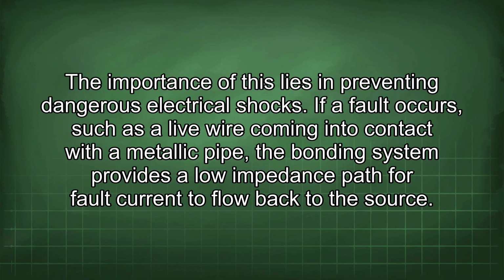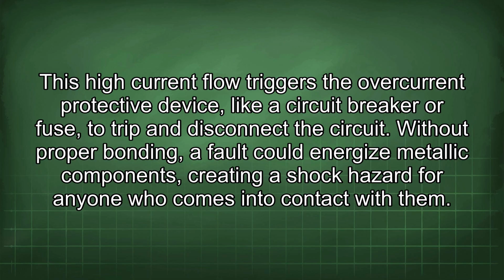If a fault occurs, such as a live wire coming into contact with a metallic pipe, the bonding system provides a low impedance path for fault current to flow back to the source. This high current flow triggers the overcurrent protective device, like a circuit breaker or fuse, to trip and disconnect the circuit. Without proper bonding, a fault could energize metallic components, creating a shock hazard for anyone who comes into contact with them.